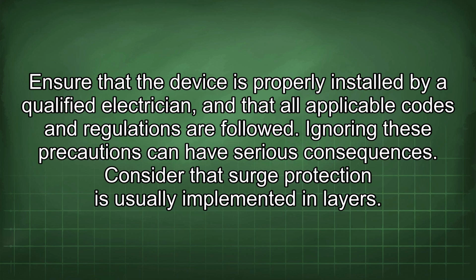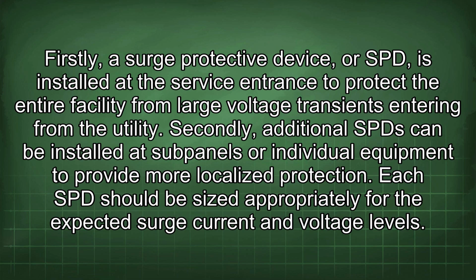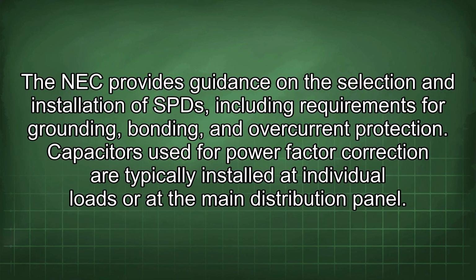Consider that surge protection is usually implemented in layers. Firstly, a surge protective device, or SPD, is installed at the service entrance to protect the entire facility from large voltage transients entering from the utility. Secondly, additional SPDs can be installed at subpanels or individual equipment to provide more localized protection. Each SPD should be sized appropriately for the expected surge current and voltage levels. The NEC provides guidance on the selection and installation of SPDs, including requirements for grounding, bonding, and overcurrent protection.